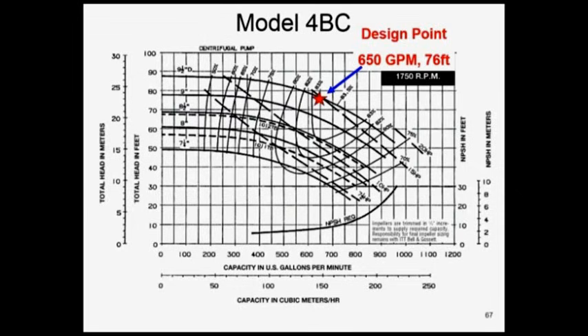Horizontally, you see the flow rate in GPM on the bottom. Vertically, you'll see it in meters and in feet of head. In this case, we're looking for 76 feet of head, going off to the vertical axis. Perfect. By the way, we're at about 83 points of efficiency. Not a bad-looking little pump. Okay, great. That's what's specified. That's what we got. That's what's on the drawings.